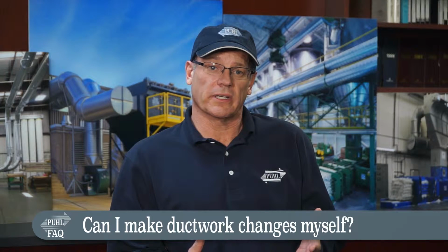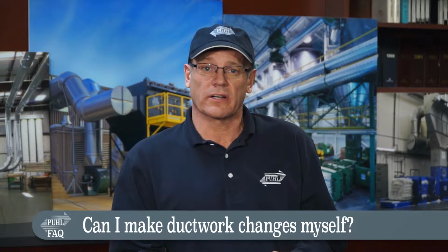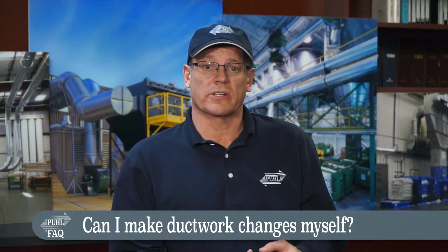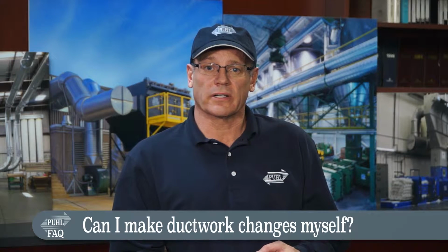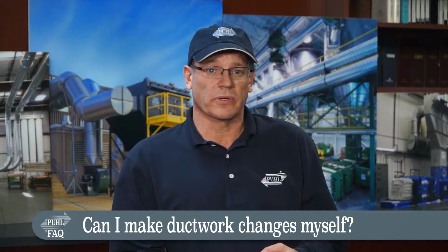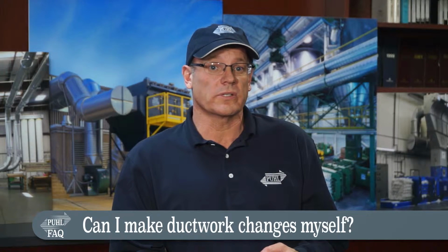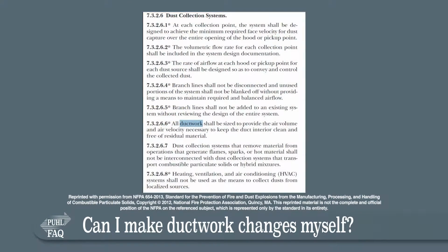This is important because duct fires are relatively easy to start and very hard to contain once started. Many times, the ductwork is in the ceiling and there are no access points, or the ductwork is on the roof and no one notices until it's too late. The NFPA regulations speak to this in Section 7, where it says that ductwork should be sized to provide air volume and velocity necessary to keep the duct interior free of residual material. They also specify that the ductwork should be inspected once per year for accumulations.